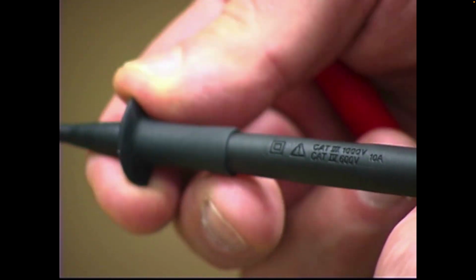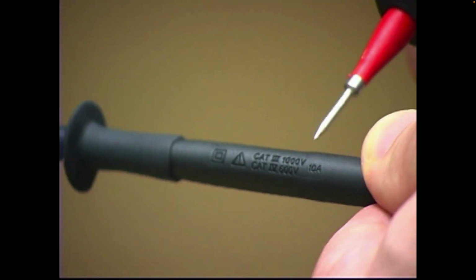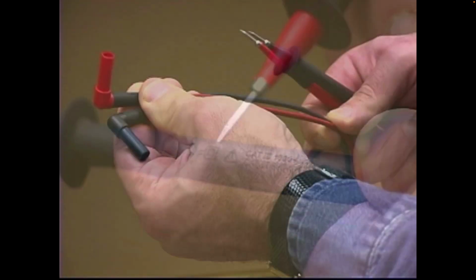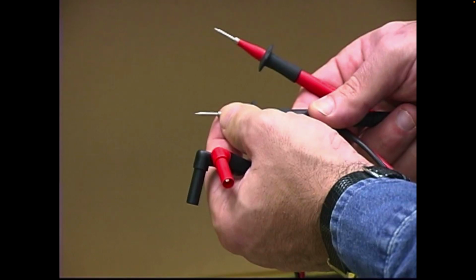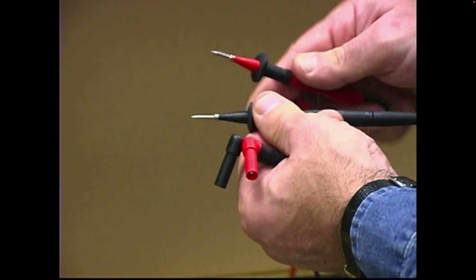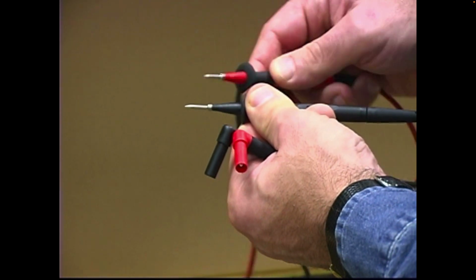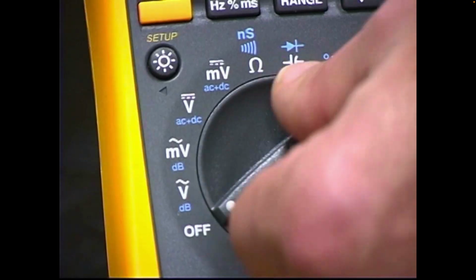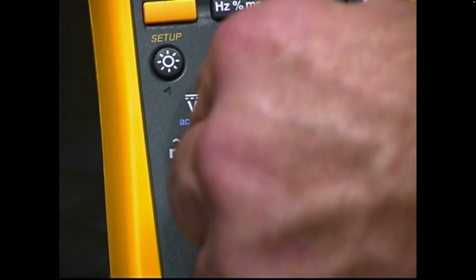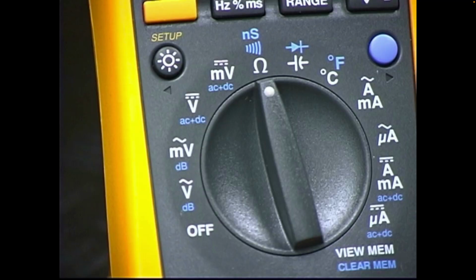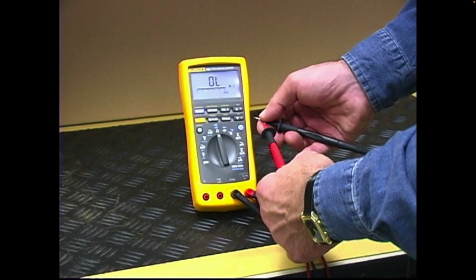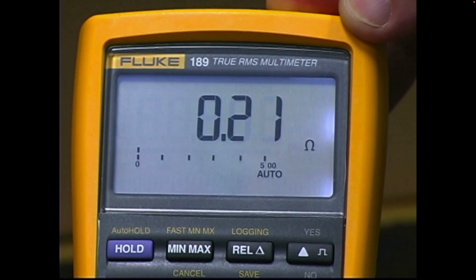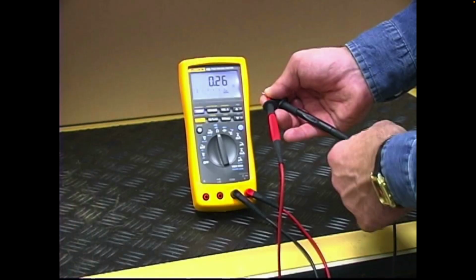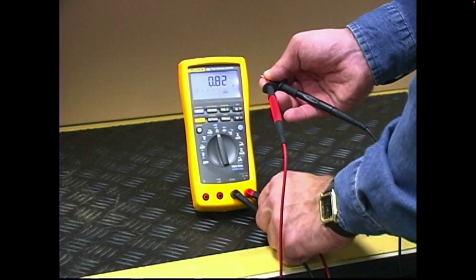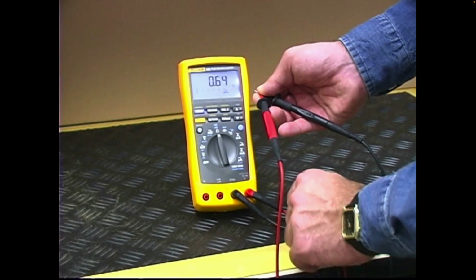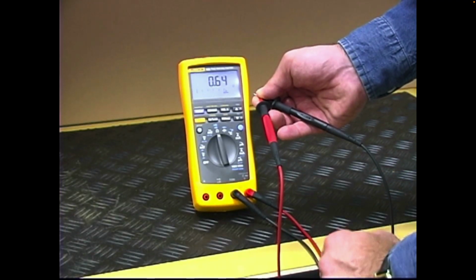Examine your test leads for such features as finger guards, cat ratings, and double insulation, and look for frayed or broken wires. Check the length of exposed metal. You can use your meter to check for internal breaks in your test leads. Turn to the ohms function. Then, short your leads together. The meter should read close to 0. With the leads still shorted, jiggle the leads and look for an intermittent open circuit, which could signal an internal break.